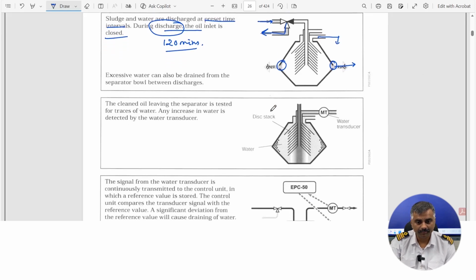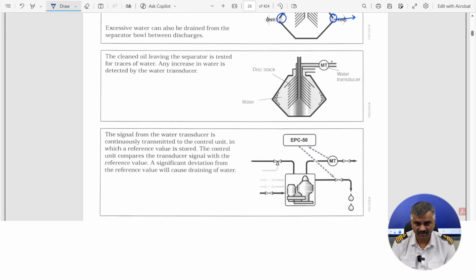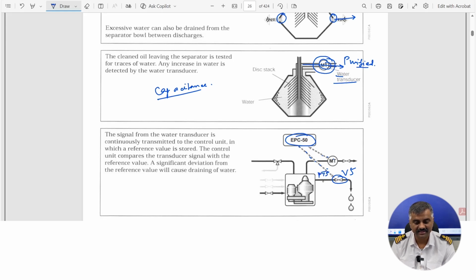Then water is also discharged, but only when there is a signal. This is the water transducer in the purified oil outlet line. In that line you have a water transducer, MT50. It works on the capacitance principle. As the capacitance of water is more than oil, this transducer measures the higher capacitance. EPC50 is the control unit. So we can see here that MT50 has measured that water content has increased in the clean oil outlet line, and EPC50 has opened the pneumatically operated valve V5. This is the drain valve. There is also a PT5 pressure sensor to show how much pressure there is in the drain line.